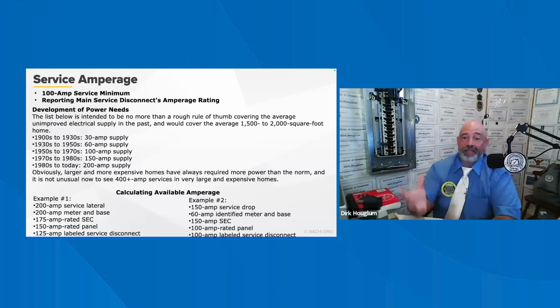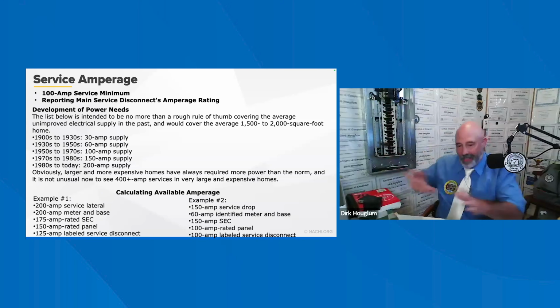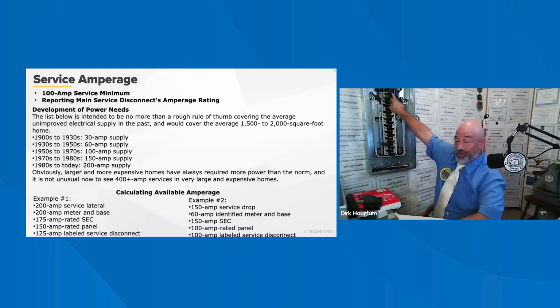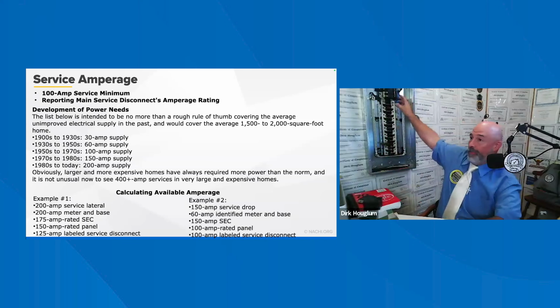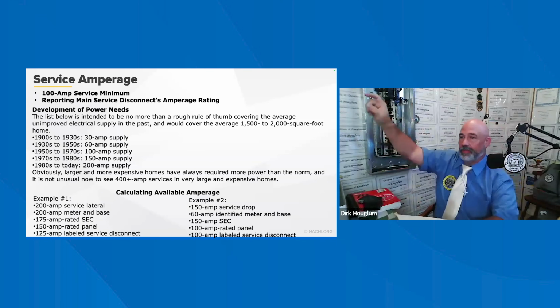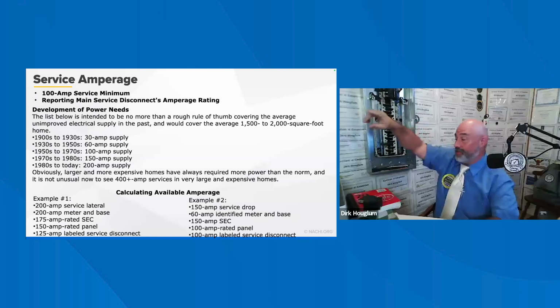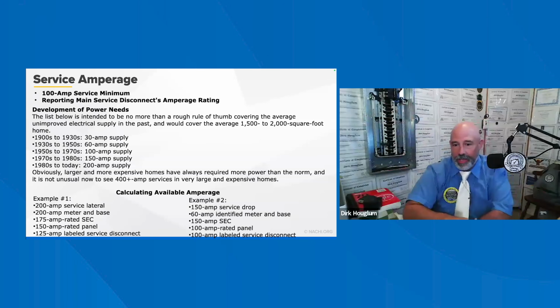So, in many cases, the listing information about the home may not be correct regarding the service amperage, because brokers or owners rely solely on the size of the main breaker or fuse. Many people are also under the mistaken impression that their total available service amperage is the total of the individual breakers or fuses in the panel. So if I have 20, 20, 20, 20, 20, add those all up, that's not right, because it's only going to go to the 200 amp that's coming in here. And if this was a sub panel connected to a 100 amp service, that 100 amp is the lowest, that's when it's going to trip, at 100, not the 200. So kind of keep that in mind.